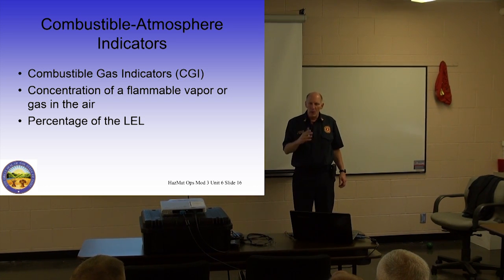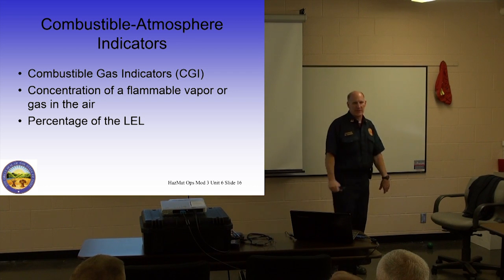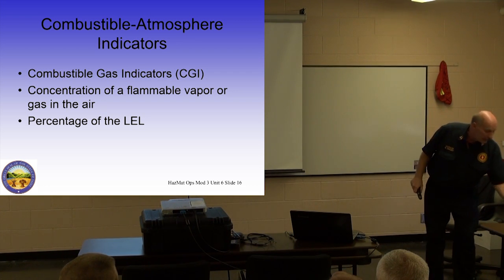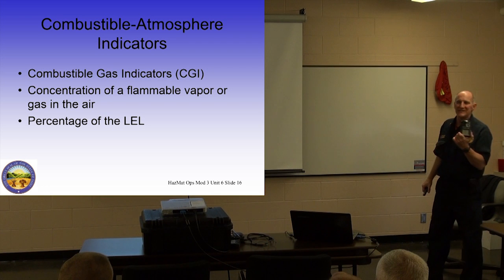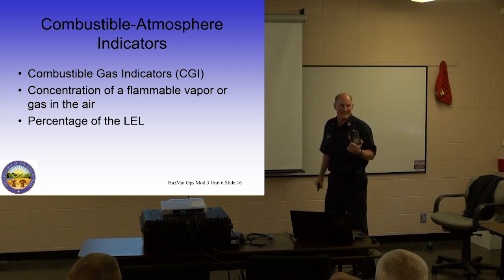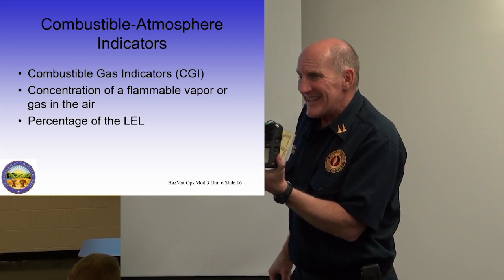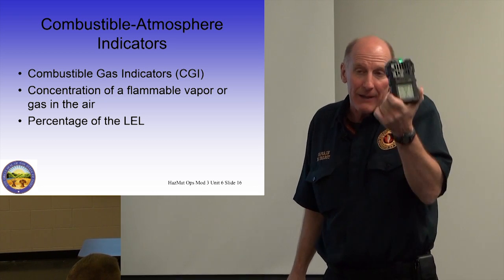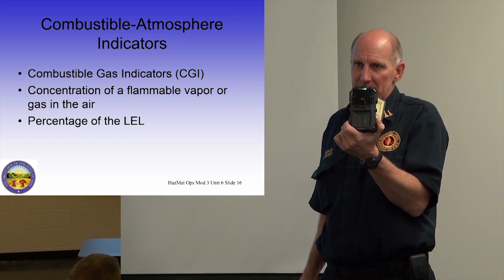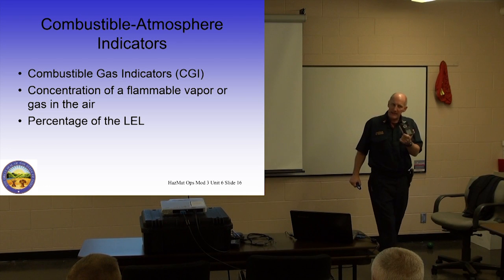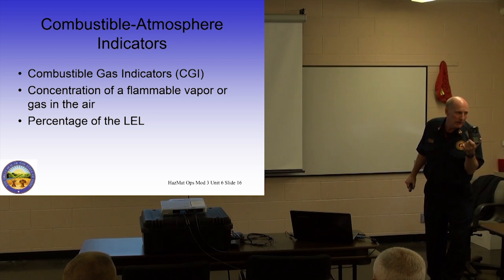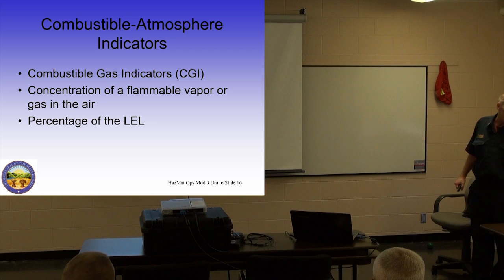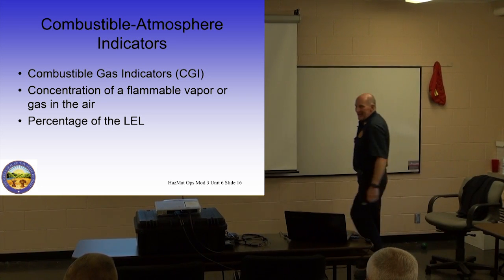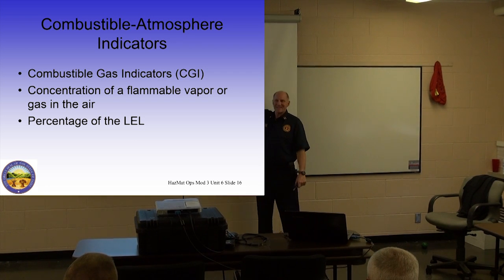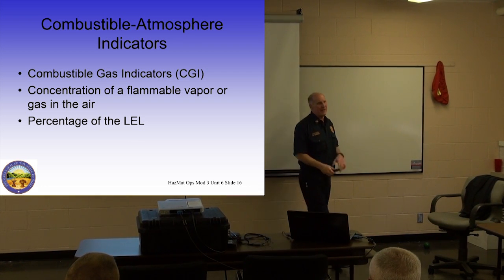Next up, the next most important thing is the LEL sensor. The next most important thing that this instrument is going to read is the potential for combustible gases. Any gas that can ignite and burn can be picked up by these instruments and give you a reading. Now, it can't read combustible dusts in the air, but it can read a combustible gas or a flammable gas that's putting off vapors. It gives you a measurement in something called a percentage of LEL.